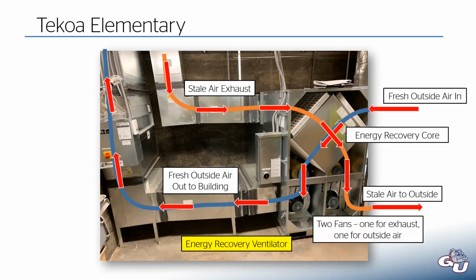So what's going on with this energy recovery core? Remember on day one, I talked about how energy intensive ventilation air is. Because if it's super cold outside, we need to heat that air up to a comfortable temperature before we send it out into the space. So let's say we have a very cold day and we're bringing in 5-degree fresh outside air, and we are getting rid of about 70-degree stale air. So that exhaust air at 70 degrees, there's a lot of heat energy in that air that a lot of times we just get rid of. We just dump it outside.